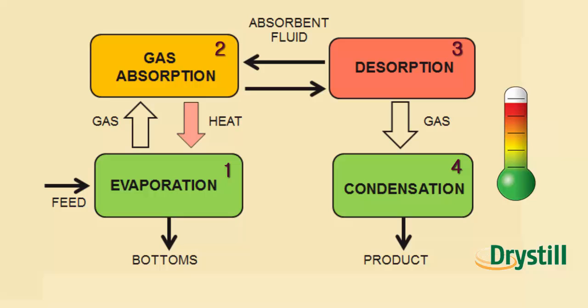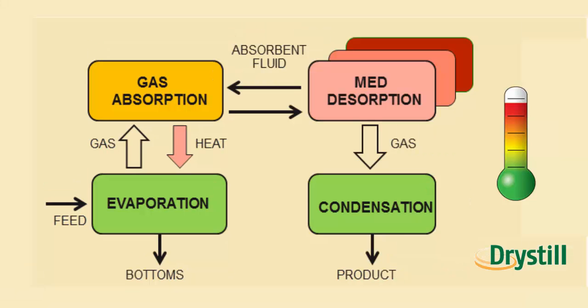The volatile components, including water, alcohols, and organic solvents, are unaffected by temperatures up to and beyond 200 degrees C. A temperature ceiling that high permits the use of multiple effect distillation, or MED, a well-known and widely used energy-saving measure.